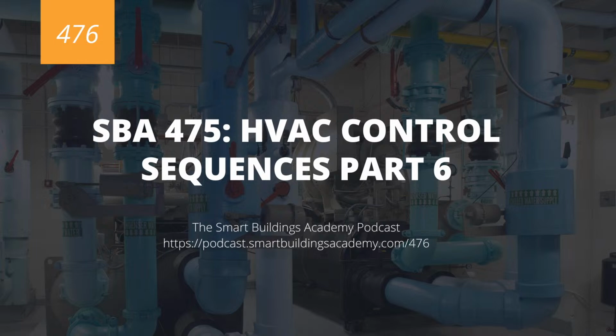So from here, we have flow status. Now, there's really two ways. There's internal flow sensors that automatically enable the chiller, or an external flow sensor that, once proven, will allow your control system to send an enable command to the chiller. You can probably guess which one I prefer. I prefer the external flow sensor. That way I know its proven status, and also, typically, the chiller has its own flow switch, so that's a secondary safety. I don't want to rely on that secondary safety. I want my primary, which is my flow switch or flow sensor, and it tells me when the pump's on.